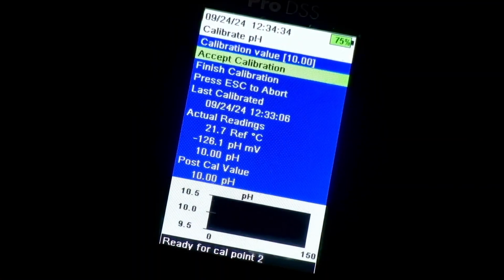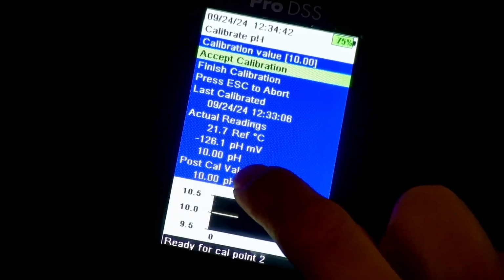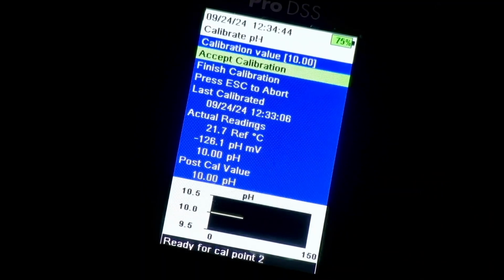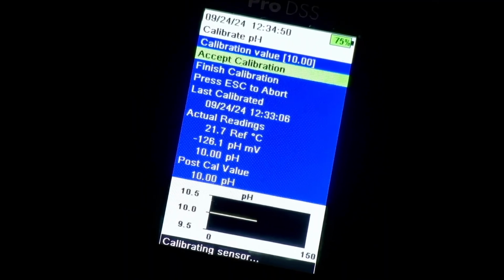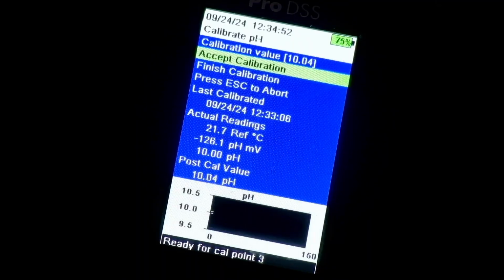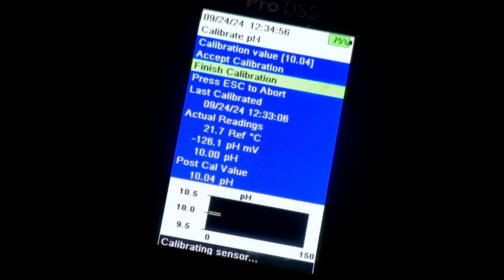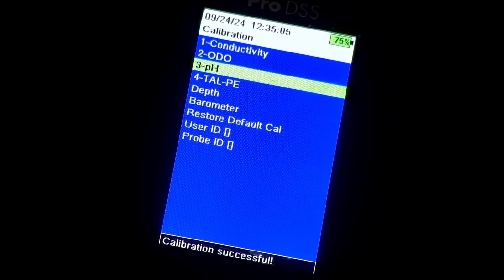Once the white line is stabilized, record the temperature along with the pre- and post-calibration readings on the calibration sheet. Then, go ahead and select Accept Calibration on the YSI. Once it says Ready for cal point 2, select Finish Calibration. The handheld should return to the calibration menu with the message Calibration Successful at the bottom of the screen.